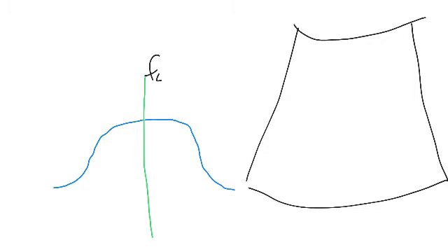With dynamic frequency tuning, what happens is a pulse is sent out from the transducer, and we know from our previous studies that there is a certain bandwidth associated with that pulse that is centered around a center frequency, which is what we would say we're scanning at typically, but that it has frequencies within it that are higher frequencies, and also frequencies that are lower frequencies.